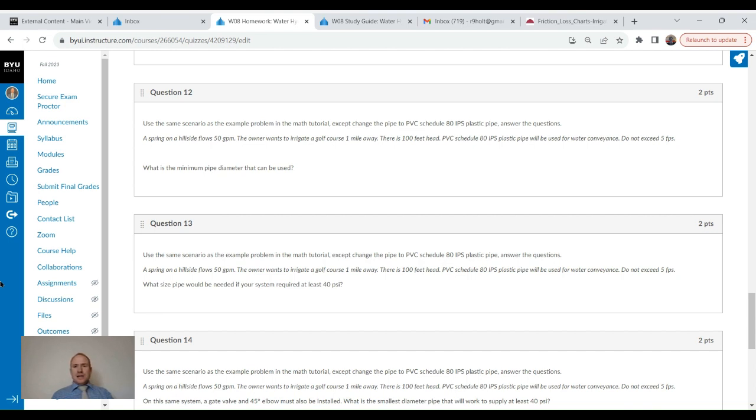Let's divide up that psi loss, so we can really figure out how much we can lose per length. So if I go 52.8 lengths and divide that by our 3.3, okay, sorry, I did that backwards. Go 3.3 psi and divide that by 52.8. And that's going to tell us that per length of pipe we're willing to lose 0.0625 psi. That's our limit. That's our maximum loss per 100 feet. All right, perfect, good to know.